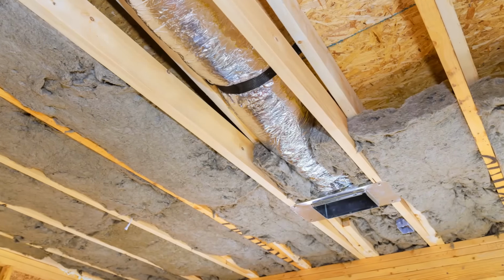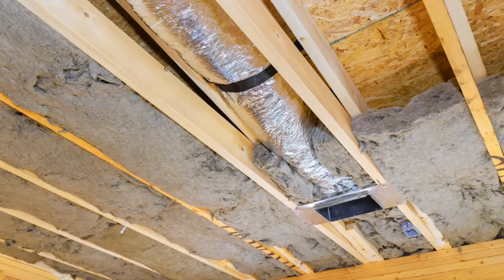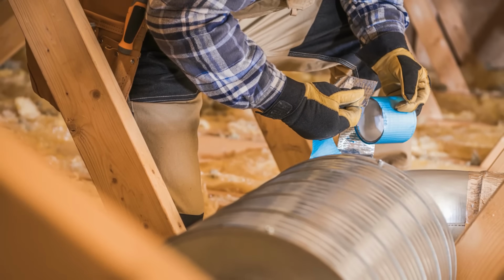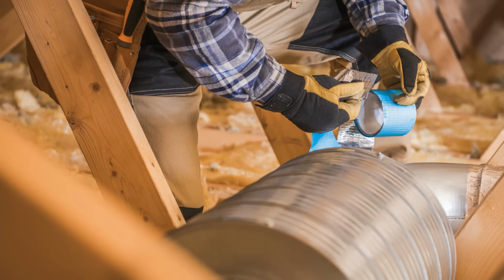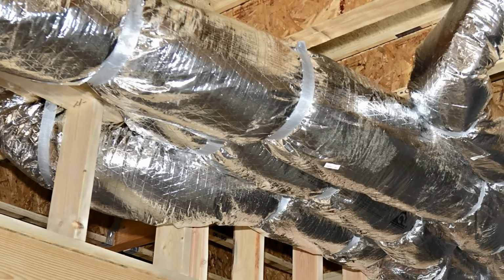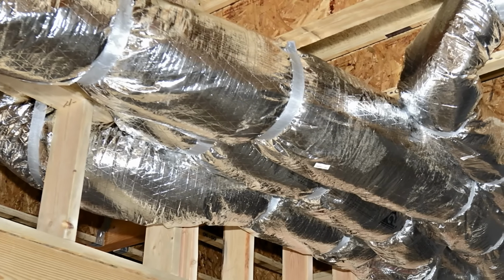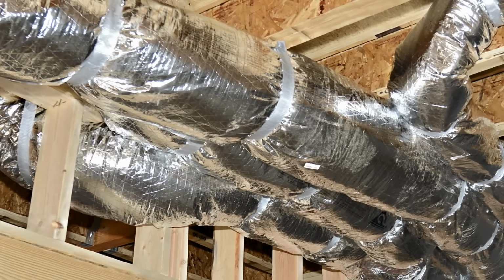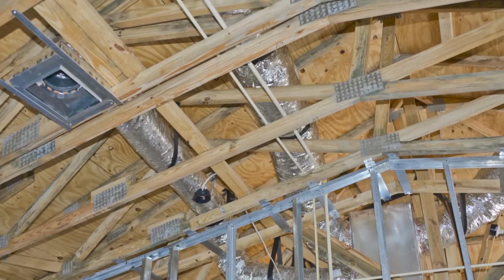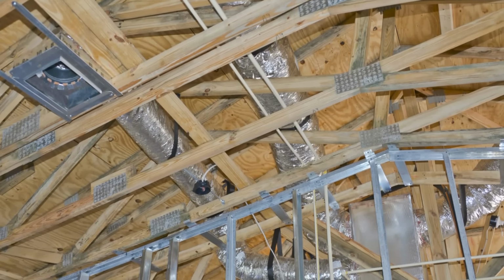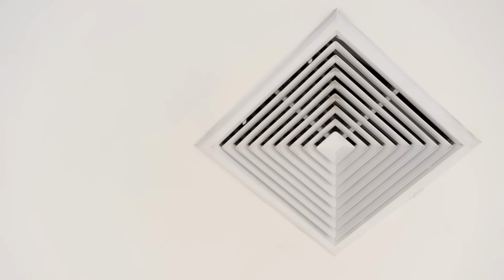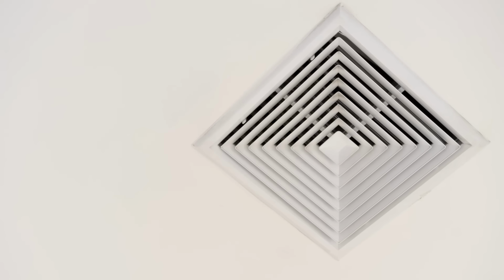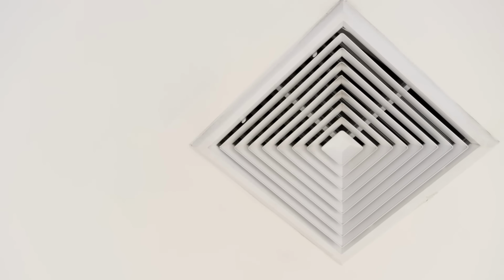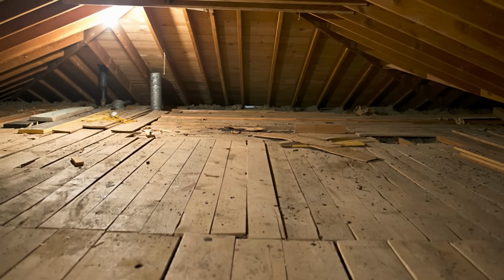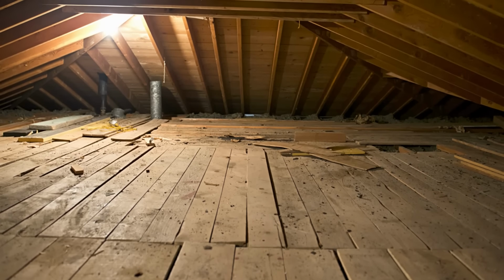We also need to talk about duct leakage and pressure imbalances. In reality, it's incredibly difficult to build a 100% leak-free duct system. Historically, attic ducts leaked around 20%. Today, we've got it down to between 5% to 10%, which is very good but still flawed when they're located outside of conditioned space. When return or supply ducts leak inside a vented attic, you're either throwing conditioned air directly to the outdoors or sucking unconditioned, dusty attic air straight into your breathing zone.